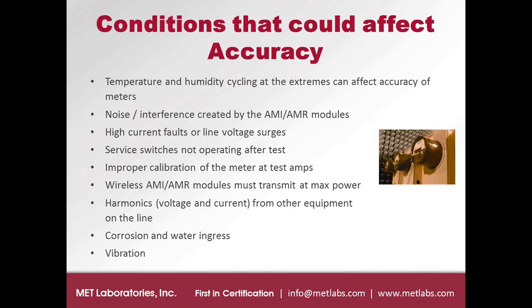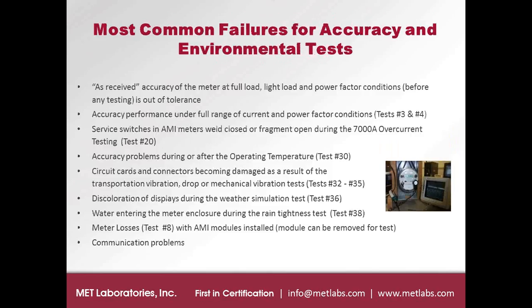Corrosion, water ingress, vibration. We've all seen these types of things cause problems with the meter and affect accuracy. From my lab's perspective, the accuracy and the environmental, some of the problems we see more often happening are the meters coming in either not properly calibrated, they're out of tolerance at that full load, light load, power factor, or perhaps they don't communicate properly before the test. When we see that, we're catching it right away and not getting into the test program.